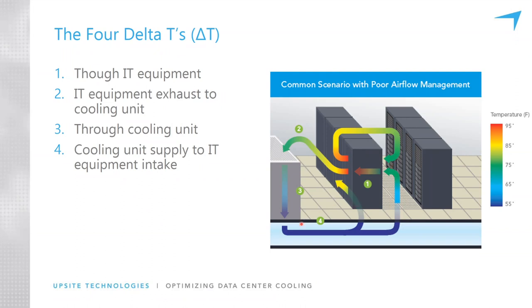The way to reduce delta T4 is with airflow management improvements, making sure that all the cable openings are sealed, making sure that all the cabinet spaces are sealed. And then the focus of our presentation today has been making sure there's aisle containment, doors on the ends of the row, something over the top of the cabinets or containing the hot air so it can't get back into the cold aisle. Eliminating exhaust recirculation is the only way to reduce delta T4.